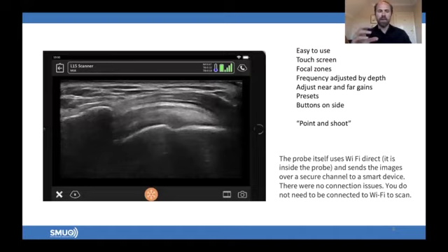In terms of the presets, there are lots of presets for MSK, shoulder, nerve, exactly what you would expect. And they all seem to work reasonably well. One thing you can't do is alter the frequency manually. So basically, if you change the depth, it goes to a lower frequency, obviously for your deeper structures. And if you go to more superficial depths, then obviously the frequency will go right up to that sort of 15 in the case of the L15, or 13 in the case of the L7.